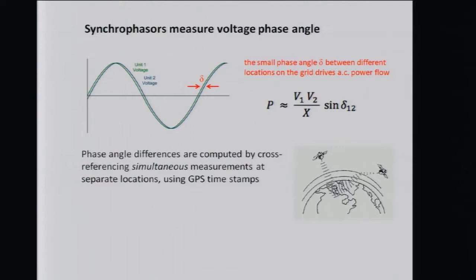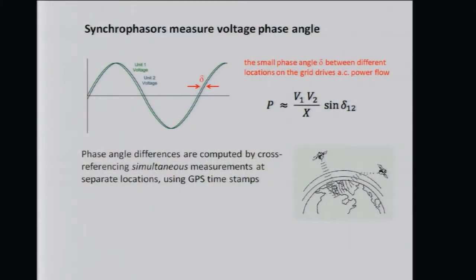Now, to measure this was not possible until we had GPS satellites and a precise time reference that you could share between different locations. Because clearly you need to agree on exactly what time it is between two locations when you're measuring the voltage crossing zero or reaching its maximum, so that you can actually measure that shift. Before, the first synchrophasors were used in transmission systems in the 1990s. There were models that calculated these phase angles, but you couldn't really measure them empirically out in the field.